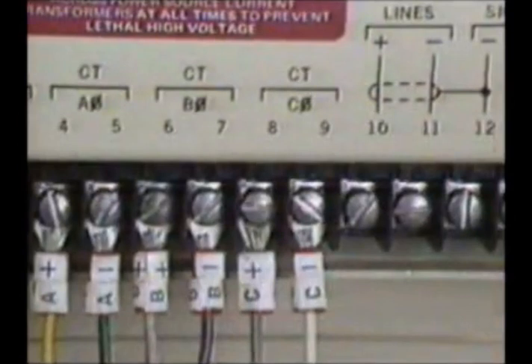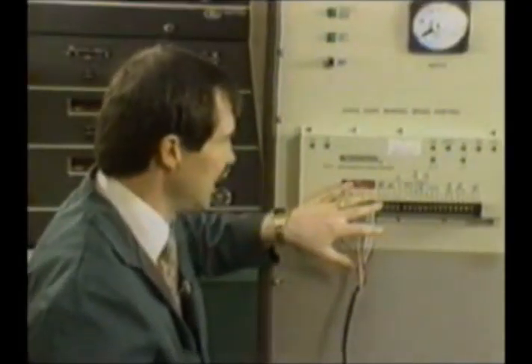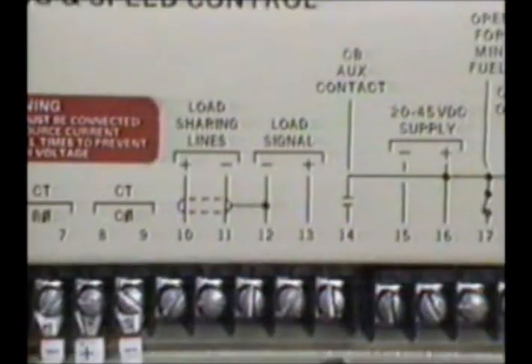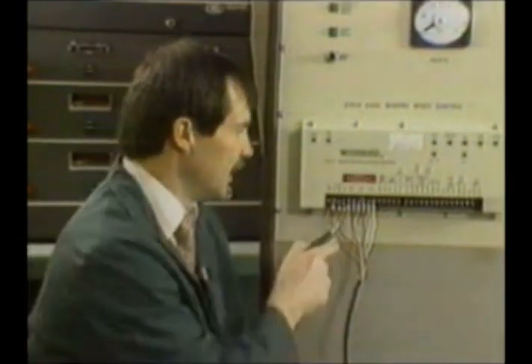So now, once I get this last one hooked in, we'll go on to terminals 10 and 11, which are our load sharing lines. First thing I want to point out about this is we should have shielded cable coming to terminals 10 and 11, with the shield connecting to terminal 12.